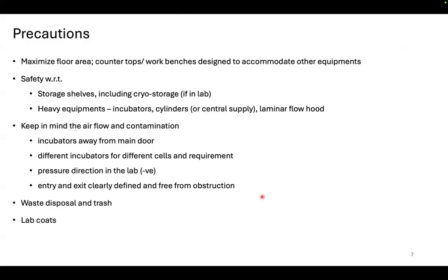So the airflow should not go out from the system. Just keep this in mind. The other thing is there's going to be one or more doors that lead to where you're working. So the incubators and your laminar flow hoods, where you're working, should be away from the main door so that there's no air coming directly.